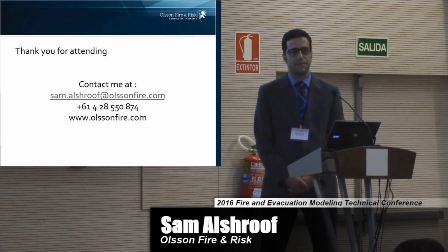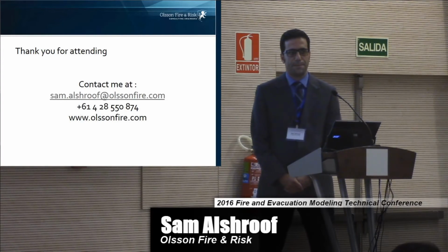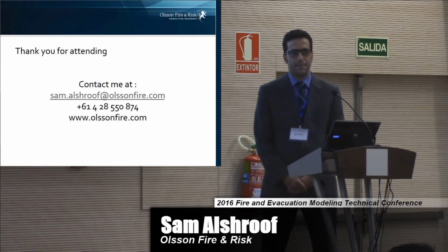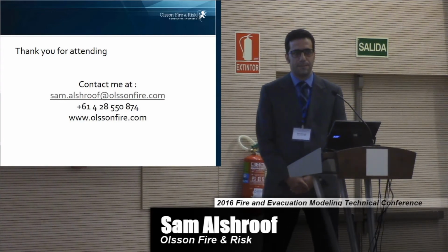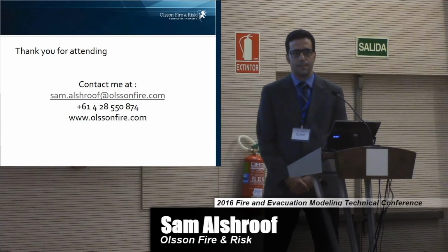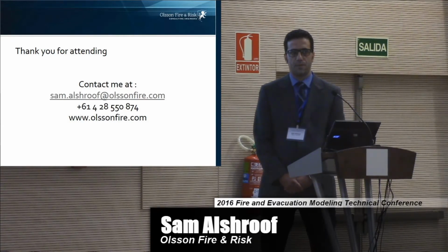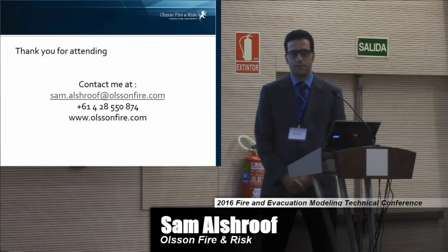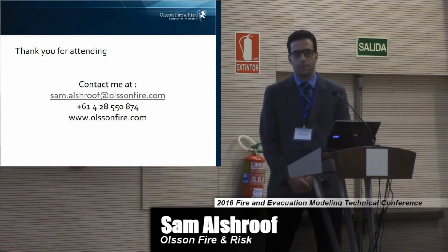Yeah, I would like to make a couple of observations. I think you've shown velocities, while it would be more interesting to see induced flow, because we are talking about the flow induced by the JETFAN, which is not the velocity, because you could have a good volume flow even if the velocities differ.